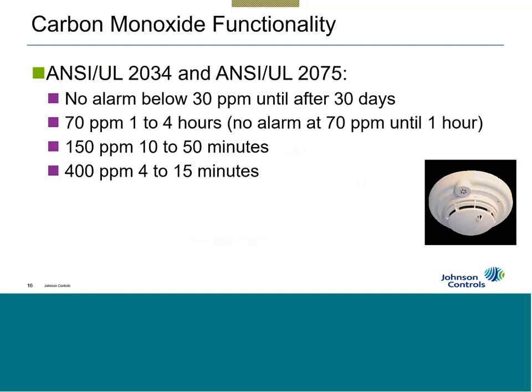So I go as Johnson Controls with my product to Underwriters Laboratory, and I say, okay, I want this device listed to UL 2034 for a detector. So they put it in a room, seal it up, inject 30 parts per million, start a watch, and you've got 30 days. That's not a typo, it's days. So I cannot go into alarm with 30 parts per million in the room until after 30 days have completed. If I go into alarm on the 28th day, I failed the test.